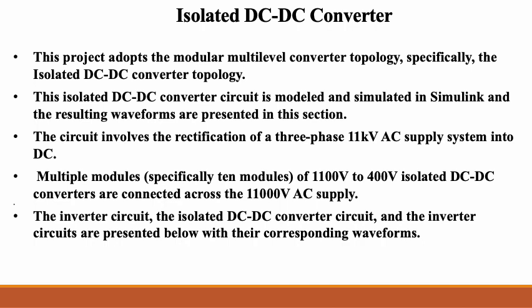We connected 10 modules of the 1,100 to 400 volt dual active bridge. The configuration was that the input side was connected in series so that we can get the capability to handle 11,000 volts, and the output side, which we wanted to still maintain at 400 volts, was connected in parallel.